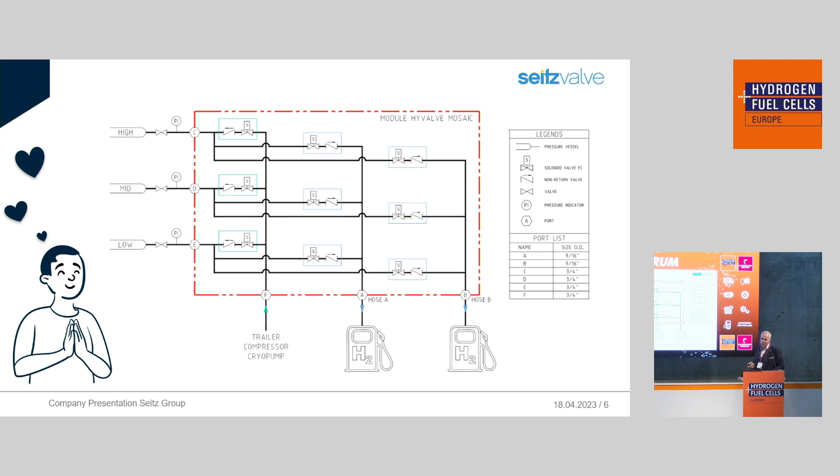Going from the 3D model of the HyVALVE Mosaic a step deeper into the system with the P&ID: the red frame contains the module HyVALVE Mosaic. On the left side you see the connection points to the storage bank, and on the bottom line you see the inlet from the fresh hydrogen and the two outlets to the dispenser. The green and blue frames show the normally closed solenoid valve as well as the check valve, with arrows showing the flow direction of the hydrogen.